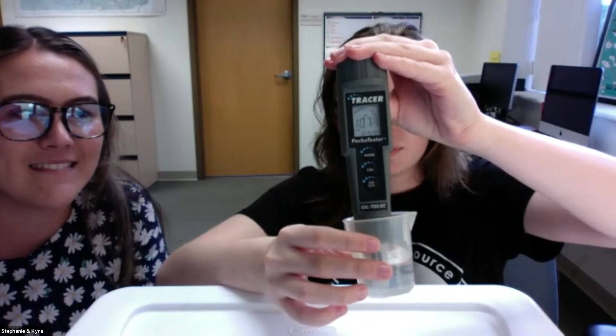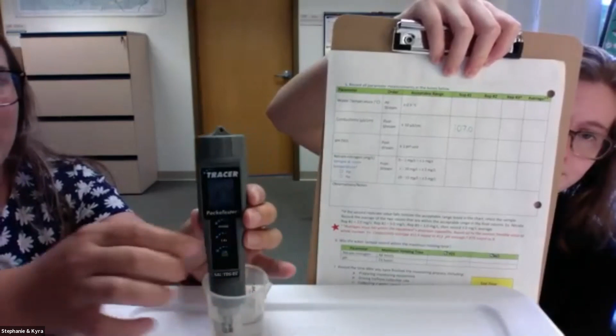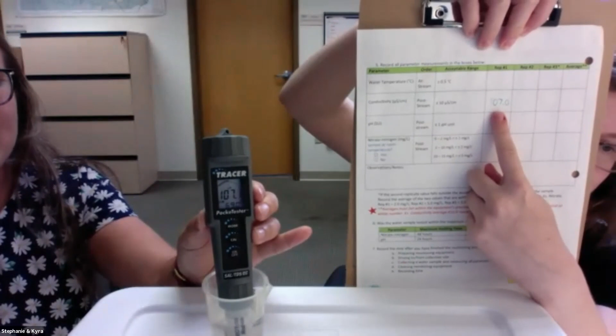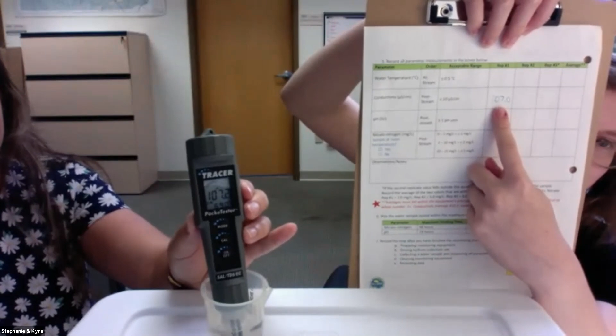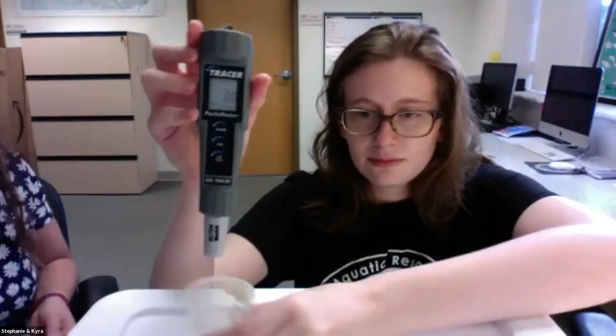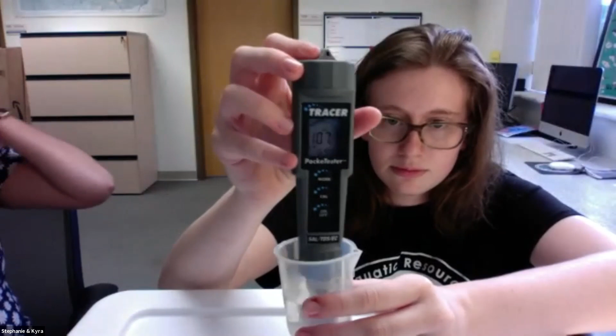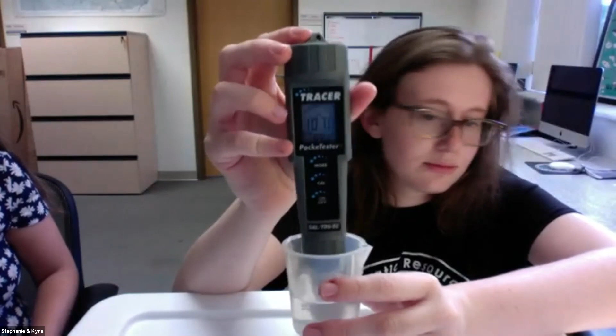So once you have a stable reading, you can record this value on your data sheet. It'll be right below where the water temperature was, and you'll do this in replicate 1. What is the value over there? We can unmute you. 107.0. Thank you. All right. And once you have recorded that value, you can remove your electrode from the water. Just like the water temperature, you want to wait for 30 seconds before inserting it into the sample again. So we will reinsert now for the sake of time, but while you're actually testing, make sure you wait 30 seconds and wait for it to stabilize again.